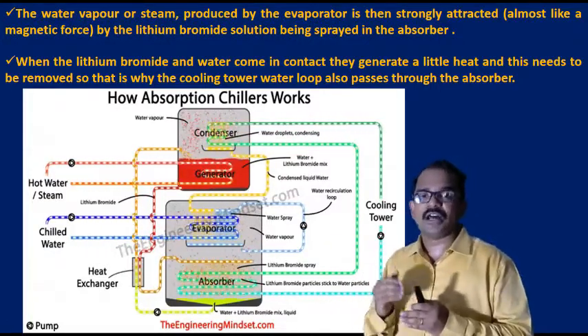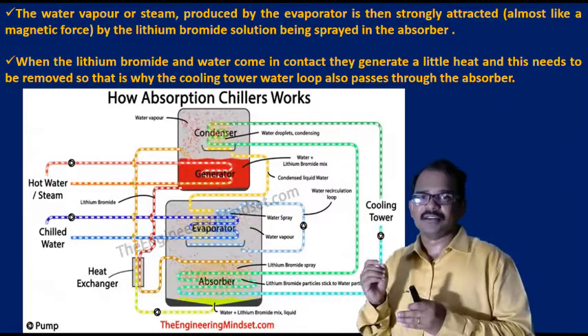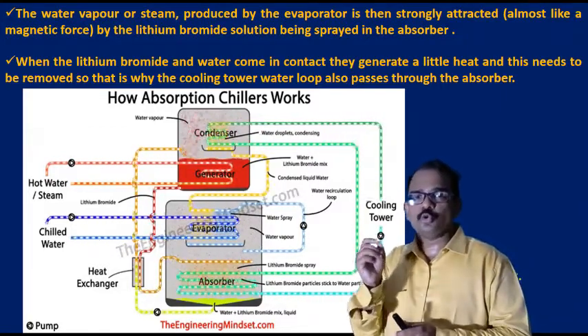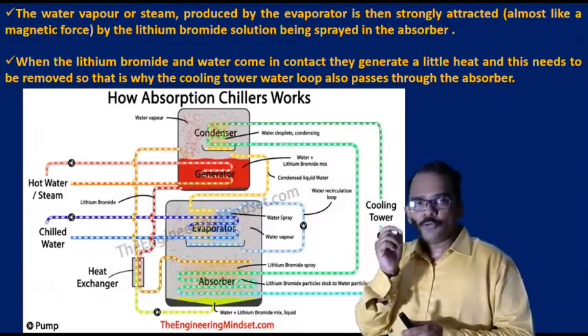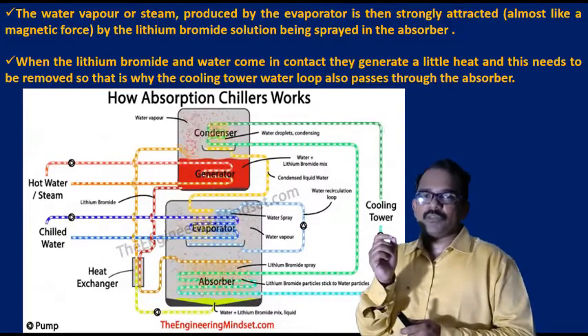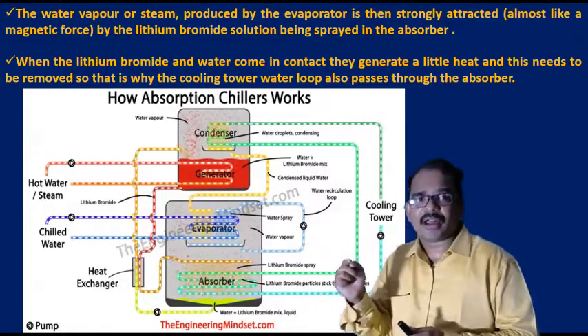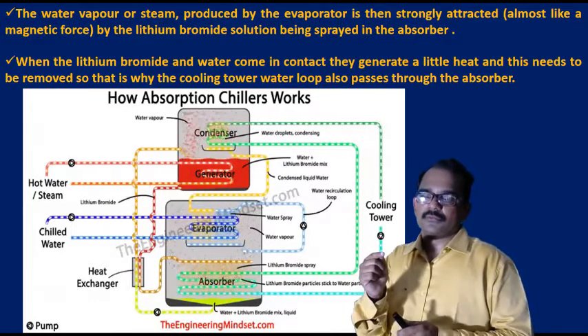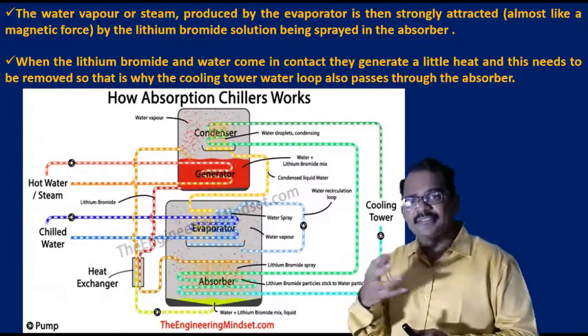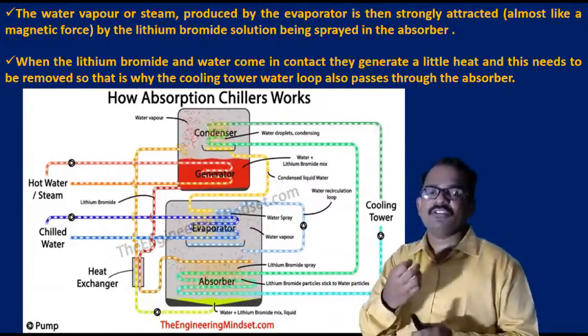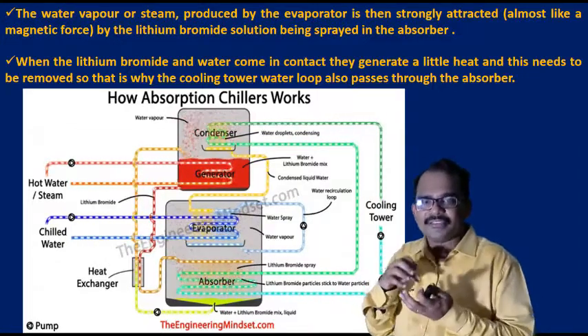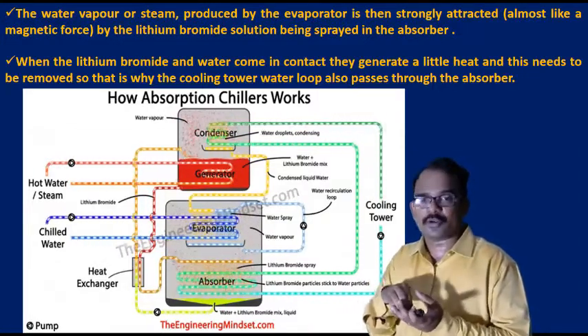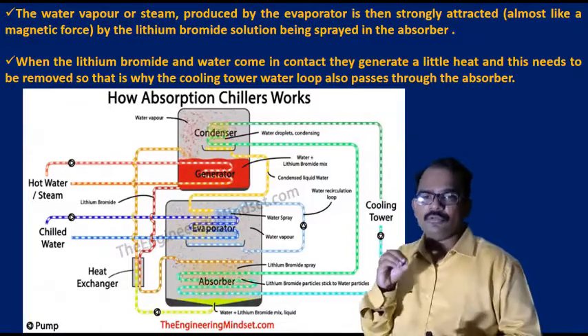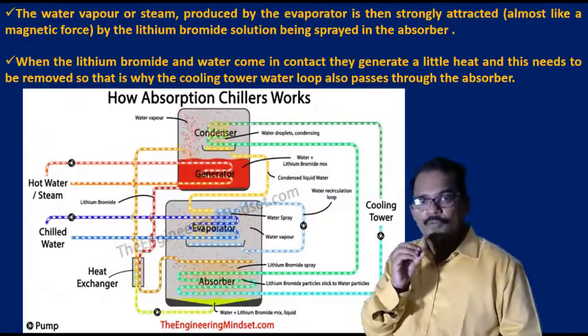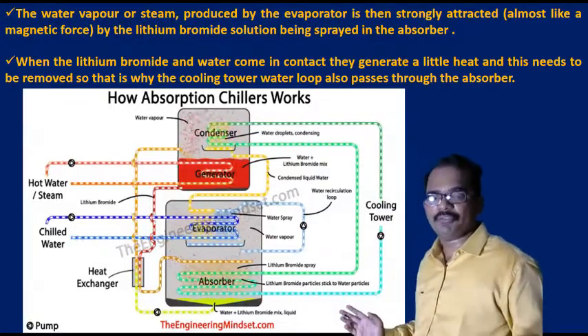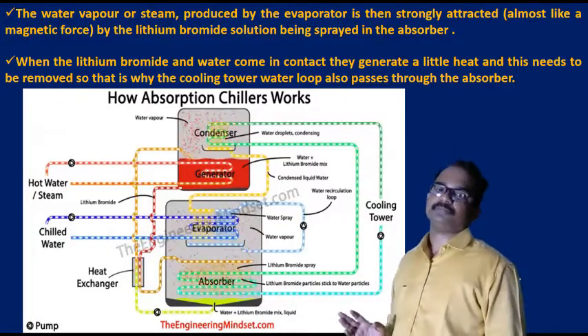But how could we do that? For that, we'll use the cooling tower water loop, and we'll make it pass through the absorber to carry away this little amount of heat which is produced because of the mixing of lithium bromide and water vapor. It is how the system will work. It is the concept of an absorption chiller.